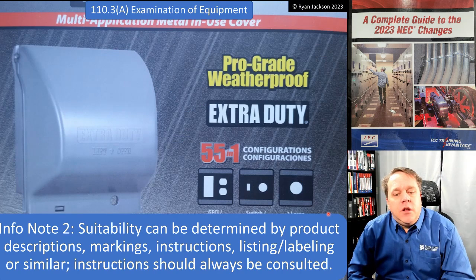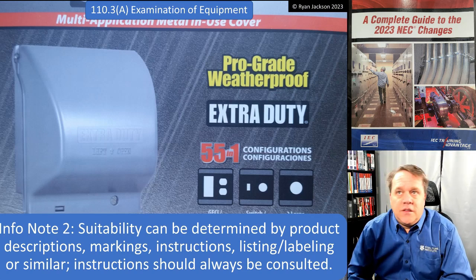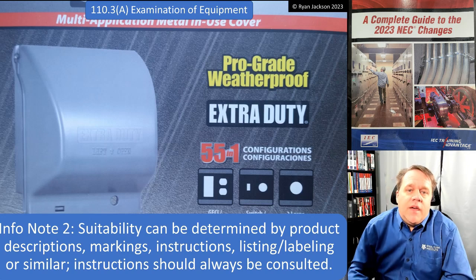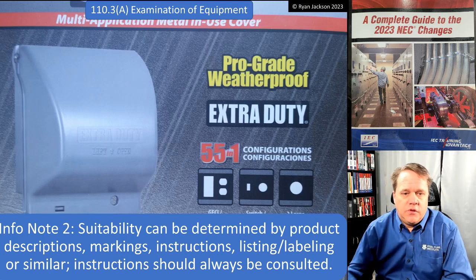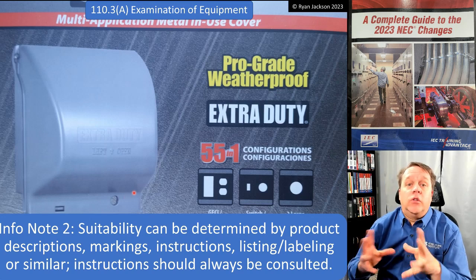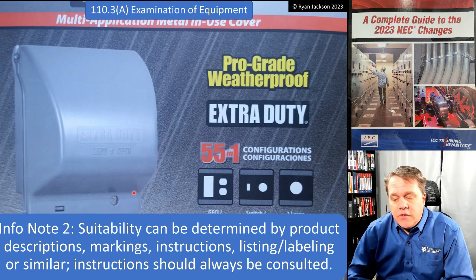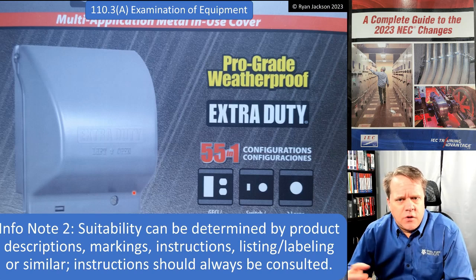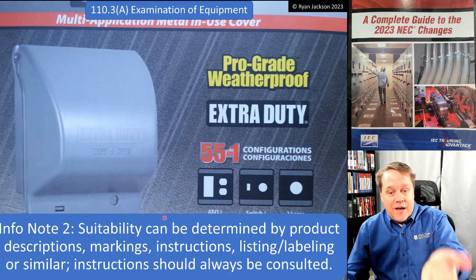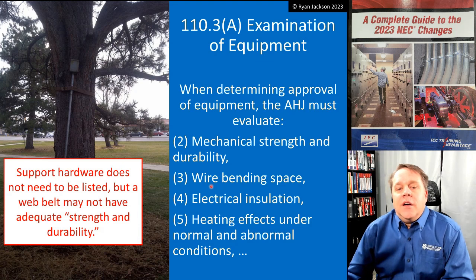Informational Note 2 says suitability can be determined by product descriptions, markings, instructions, listing and labeling, or similar. For example, Section 406.9(B) says certain receptacles in wet locations might require a cover that's weatherproof while in use — an in-use cover or bubble cover, called an outlet box hood. Those hoods must be listed and identified as extra-duty. How do I know this product is extra-duty? Because the manufacturer's marking says so. Suitability can be determined by product descriptions and markings.